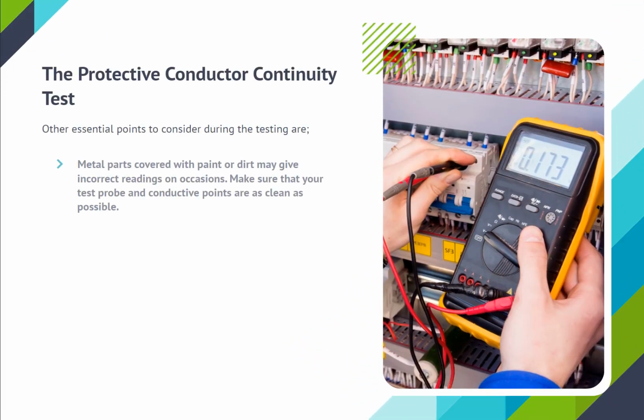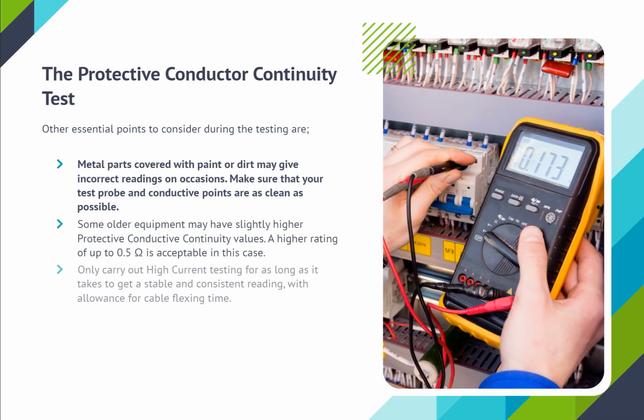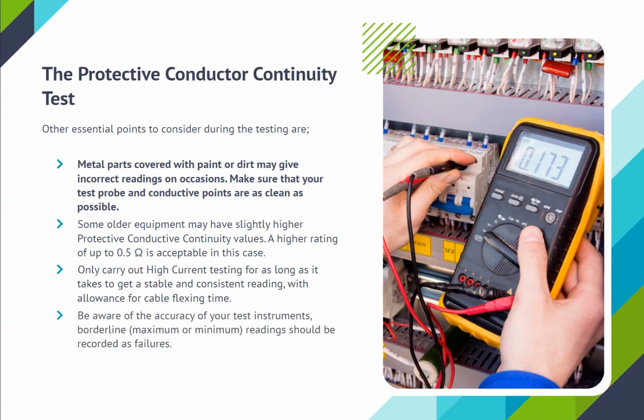Other essential points to consider during the testing are: metal parts covered with paint or dirt may give incorrect readings on occasions. Make sure that your test probe and conductive points are as clean as possible. Some older equipment may have slightly higher protective conductor continuity values. A higher rating of up to 0.5 ohm is acceptable in this case. Only carry out high current testing for as long as it takes to get a stable and consistent reading, with allowance for cable flexing time. Be aware of the accuracy of your test instruments. Borderline, maximum or minimum readings should be recorded as failures.